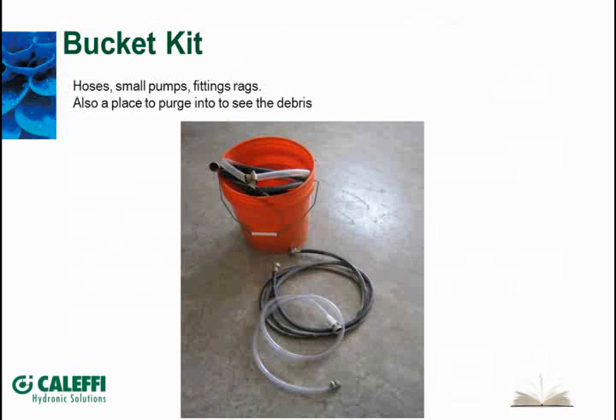And this is the simplest little kit that you can put together. Just take a 5-gallon bucket. You can buy buckets if you don't have some from the glycol. Typically comes in a white plastic bucket like this. And then what you can do is you can purge into that bucket. So when you first start filling your system, start purging into that. There you can see a clear hose there on the bottom. That one actually has some of those European-style connections on it that are a little bit different size.